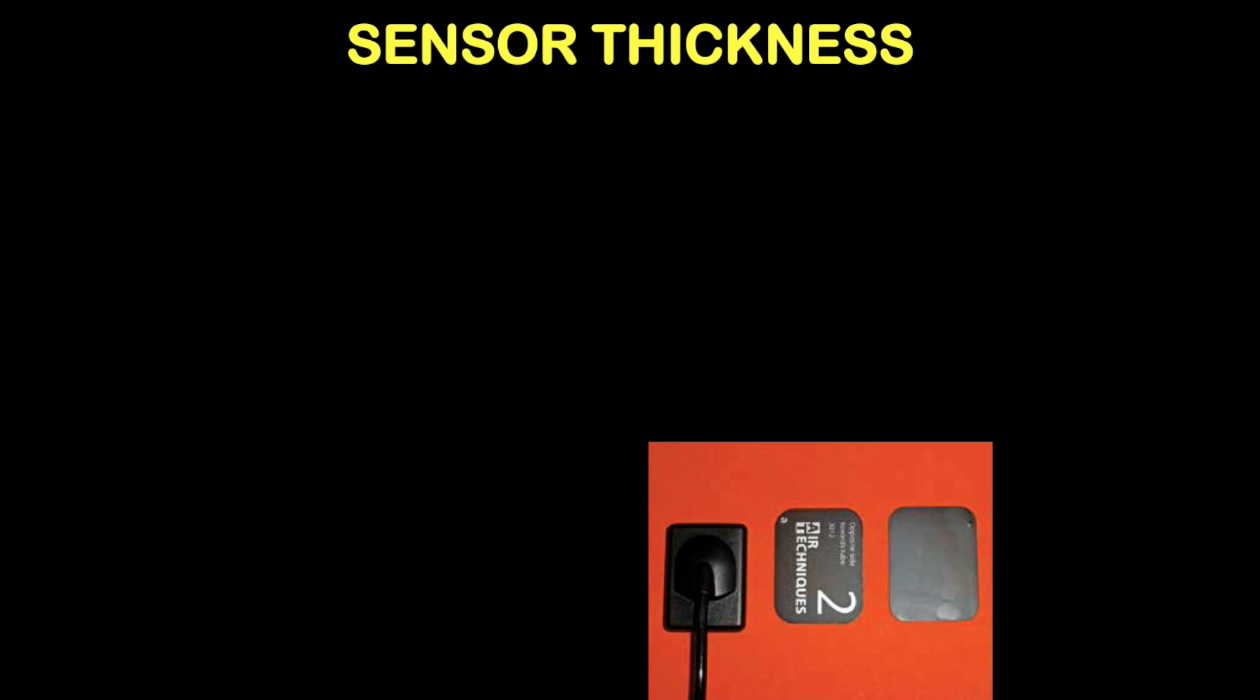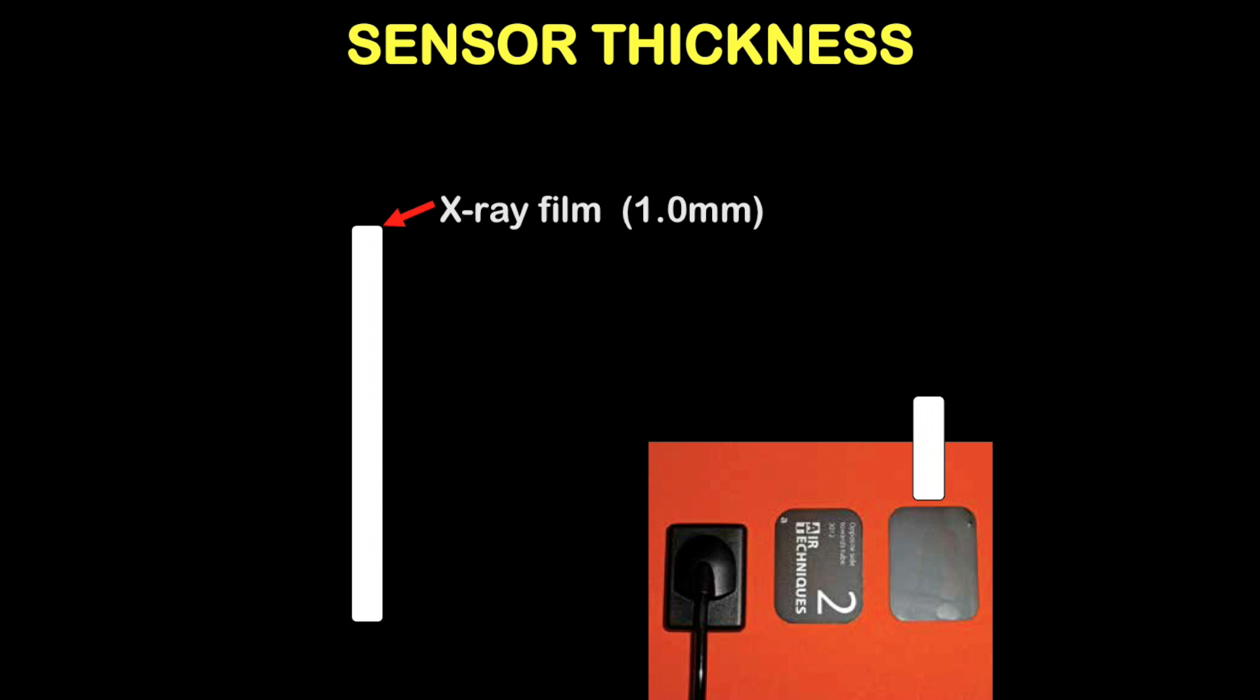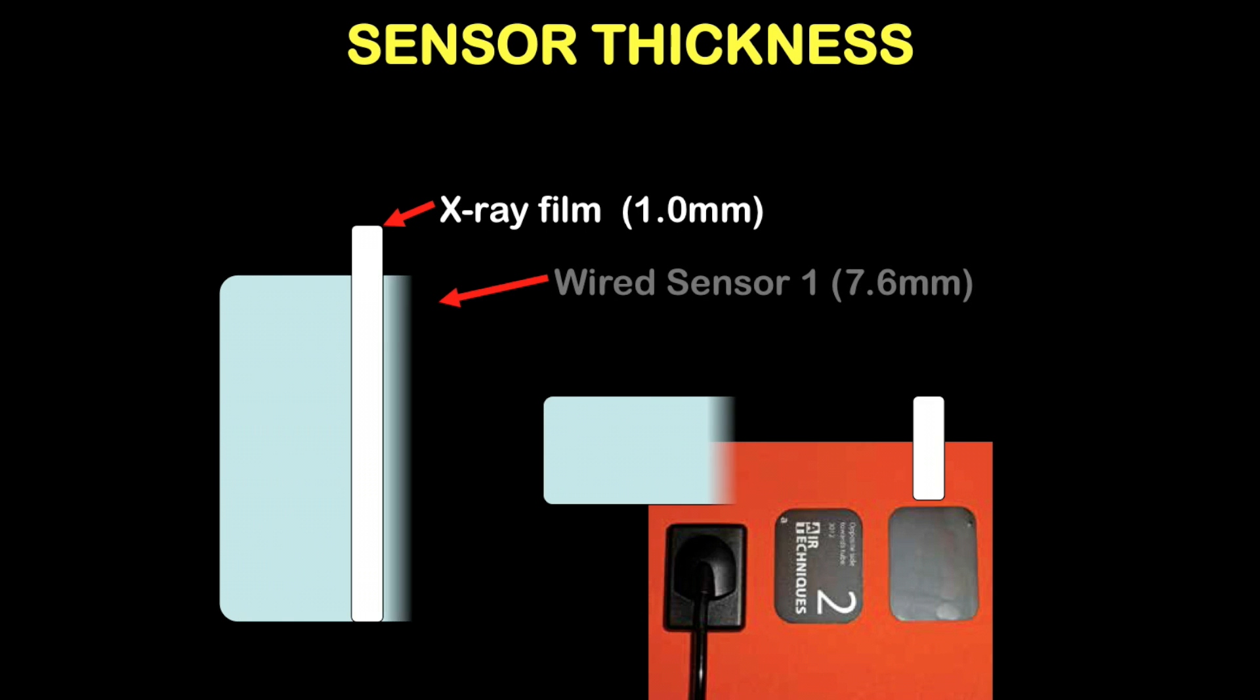The issue of sensor thickness is something that dentists and the dental team don't often worry about but is of great importance to the patient. An analog or traditional x-ray film is about 1.0 millimeters in thickness. Some of the digital sensors that are wired go from 7 to 8 millimeters or thicker.